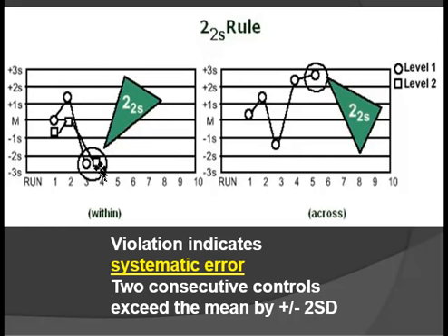Meron naman din pong ibang laboratories na they separate the chart. For example, yung first Levy-Jennings chart nila para sa normal, and then yung next is for the abnormal. Kung saan naman ang susundin, depende po sa policy or protocol ng laboratory na pinagtatrabahuhan nyo. So this one, makikita nyo, dalawang data values occurring outside the 2SD. So that's 2-2S, and that already indicates a systematic error.